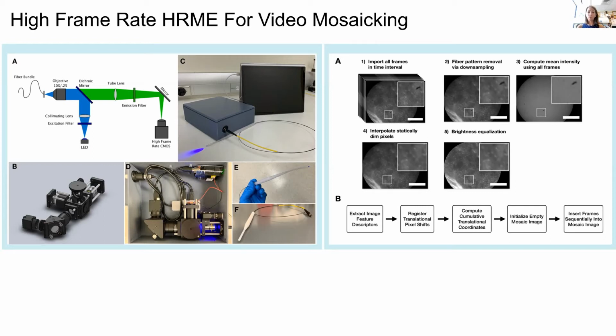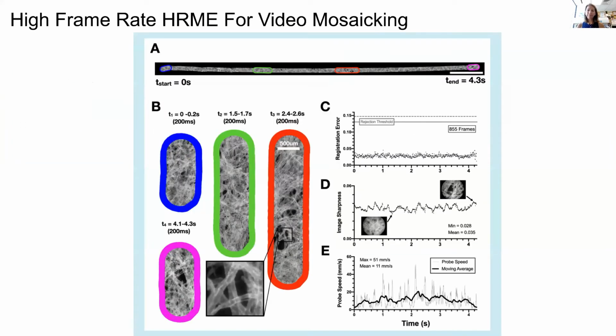So we did two things. We switched out our CCD cameras to a high frame rate CMOS sensor. These sensors can easily acquire images at 200 frames a second. And then we built a probe holder that made it easier for the operators to translate that probe across the tissue. Now we're operating this at 100 frames a second in the clinic. Then we just use simple algorithms to do co-registration from frame to frame, and we're able to build up a mosaic of a much larger area of tissue.